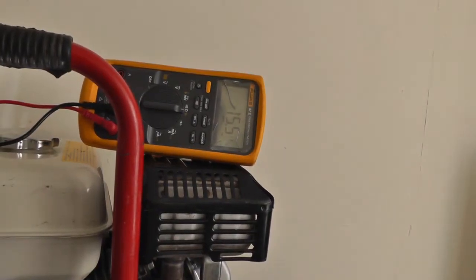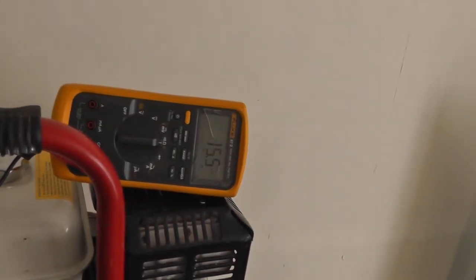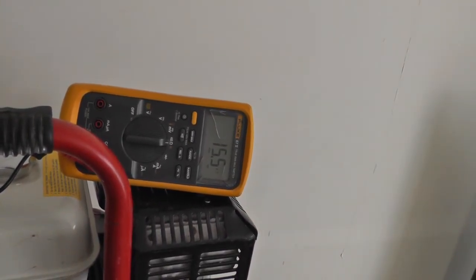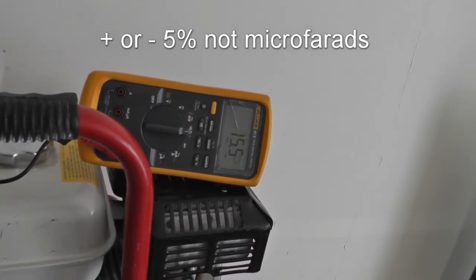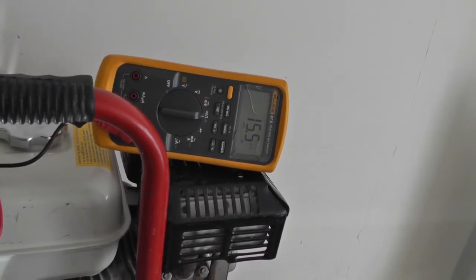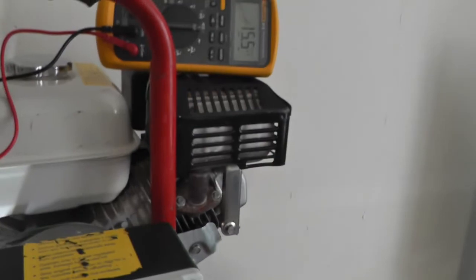I've got a reading of 15.5 microfarads on that — I'm just testing it with my lead through that hole, which is awkward. I was expecting around 18 to 20, perhaps a bit more. They have a tolerance of plus or minus five percent, so with the voltage being about five percent down it's probably about right. Anyway, I'll strip it out, get this capacitor out and get it replaced, but I'm not going to do that on video — I might do a separate video on that.